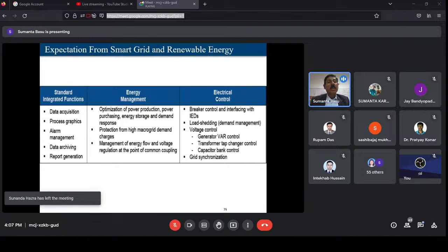So in short, the standard solutions for the smart grid will be data acquisition, process graphics, alarm management, data archiving, report generation. Energy management comprises optimization of power production, power purchasing, energy storage and demand response, protection from high macrogrid demand charges, management of energy flow and voltage regulation at the point of common coupling. Electrical controls: breaker control and interfacing with IEDs. Load shedding, voltage controls with generator VAR control, transformer tap changer control, capacitor bank control, grid synchronization. So all aspects have to be there, and this is the expectation from a smart grid.